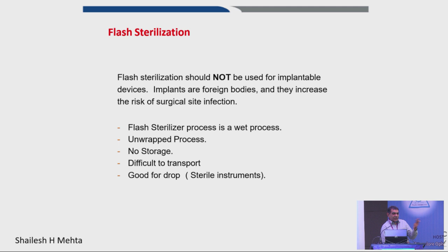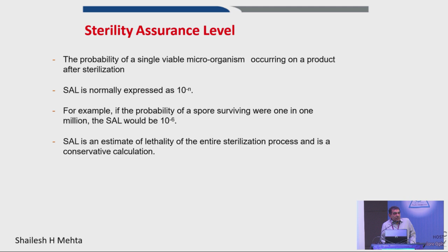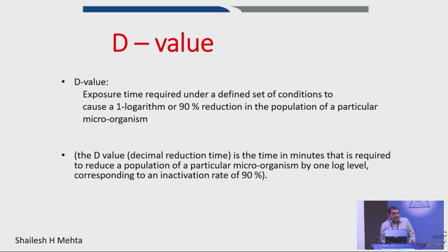Because your infrastructure, your differential pressure in the OT, your humidity conditions, correlations with CFUs, how it works, we can go deep into the subject and teach you this process. Again, your resistance of the D value, I was told to use hydrogen peroxide in one of the presentations, God bless you guys. If you're using hydrogen peroxide in an AHU, first thing is what is the humidity required. You have to reduce the humidity to 20%, then push in hydrogen peroxide. So that chemistry, in case anybody wants to learn, I can show you exactly how it works with the resistance of the bacteria.